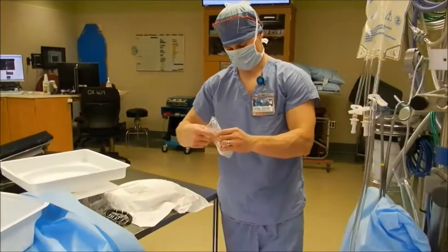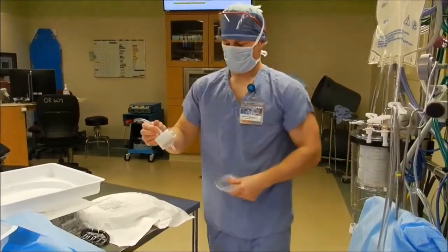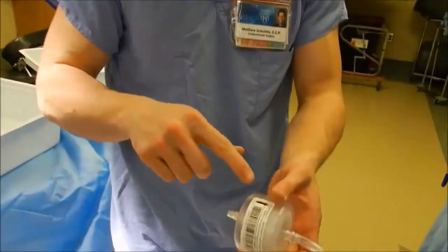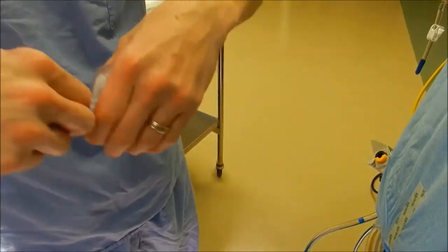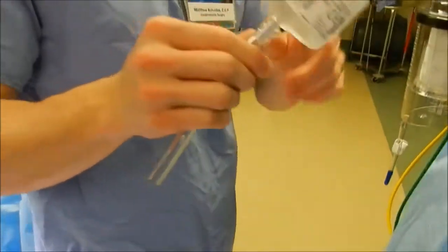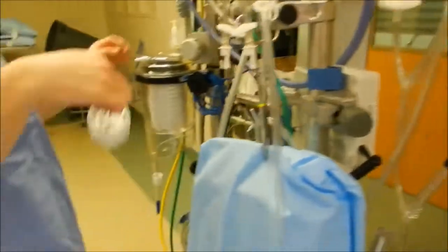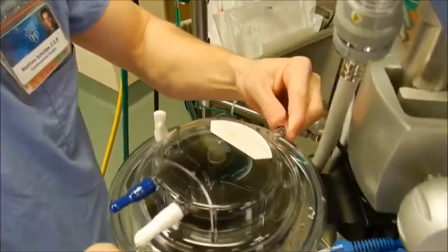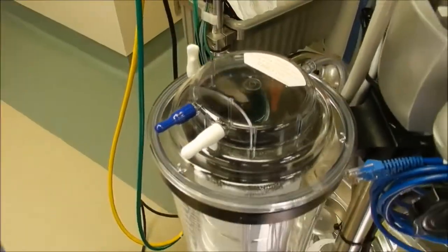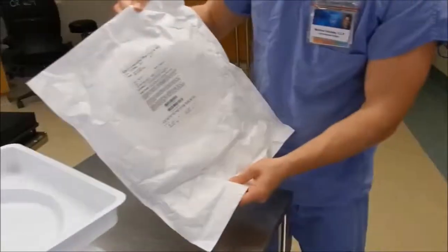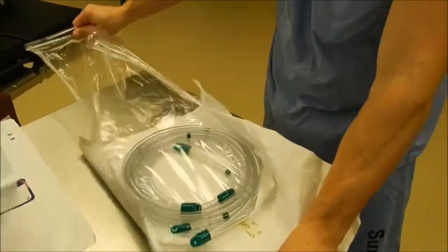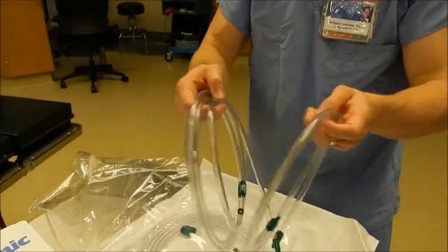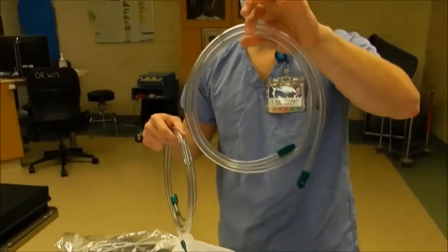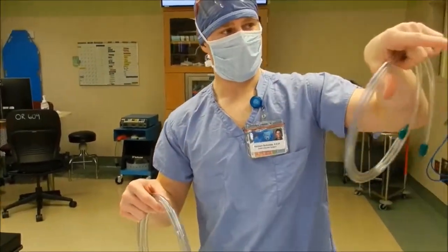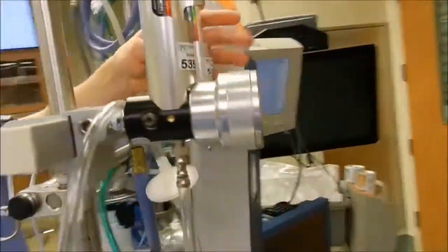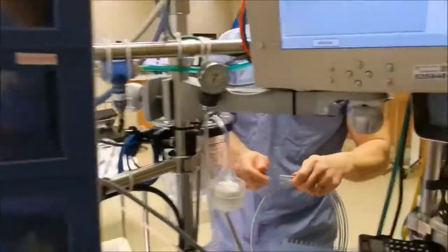We have a smoke filter which we use. Just a preference, but when this comes out, you can see it has a flow direction arrow. Make sure you check which way when you're connecting it. I typically just remove the tubing because I don't like my smoke filter in front of some of my pressure monitoring, so I move it back over here. And then save that for later. This is part of the second sucker pack we talked about for our super sucker as it's called. Comes with a couple pieces of tubing. These are longer than they need to be, but you can trim them. This will be to our vacuum source, so this will plug into our smoke filter, and then also our second vacuum connection, so we can control the amount of suction that gets taken.